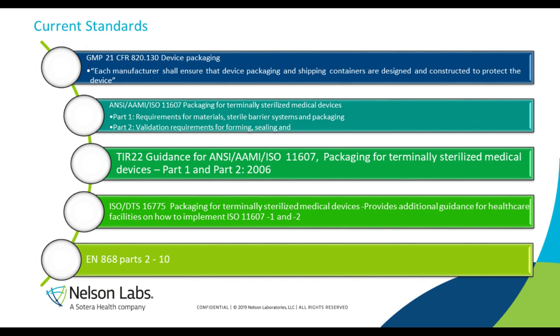TIR 22 has been withdrawn and was replaced by ISO 16775. This is also currently up for revision now and is being worked through. The last discussion, I believe, we had over 500 comments, so it's going to be a little bit before that one's finished. Then finally, the last document is EN 868, parts 2 through 10. Part 1 is harmonized with ISO 11607. So compliance to 11607 is corresponding to 868-1. Parts 2 through 10 are specific to individual material types. For example, Part 5 is specific to sealable pouches.